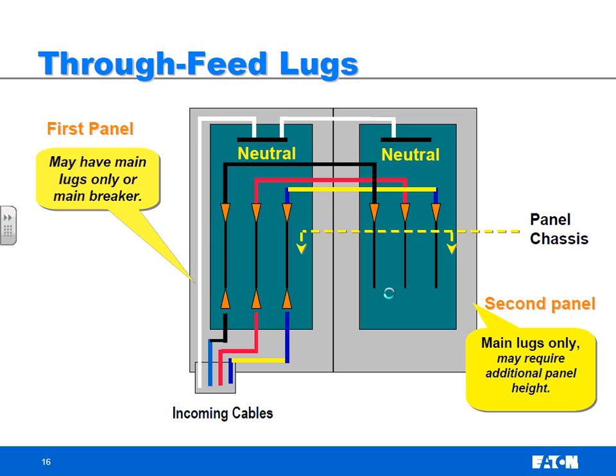Okay, so those were the sub-feed lugs. The through-feed lugs. Notice here we've got our incoming cables. We're actually putting the lugs for the second panel on the other side and making that connection over there. And why this would be an advantage, if you wanted a main breaker, you can put a main breaker here instead of main lugs, and then put your main breaker on this side, lugs on the second side, which jump right over to this one. Again, you want to keep these the same height.